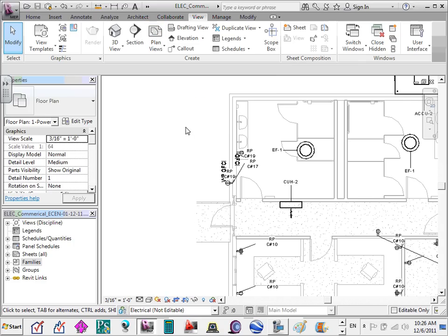Absolutely. If you don't care where your fixtures are, you drop your fixtures, they're attached to the floor, and you circuit them and print to the customer in 2D, and they have no idea, it looks beautiful. The minute you open the model in 3D, you can see that this fixture, which is supposed to be in the ceiling, is attached to the floor. Who cares if it's the floor or the ceiling? Revit is supposed to have collision detection between your mechanical system and electrical system. How are you going to have collision detection between the lights above your head and the mechanical fixture when they're on two different levels? It defeats the purpose.